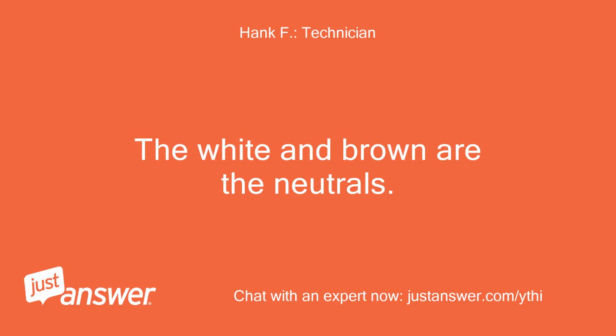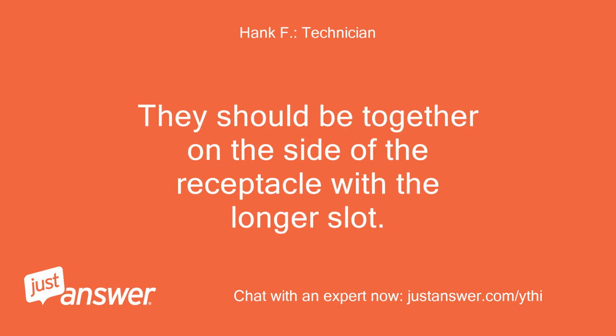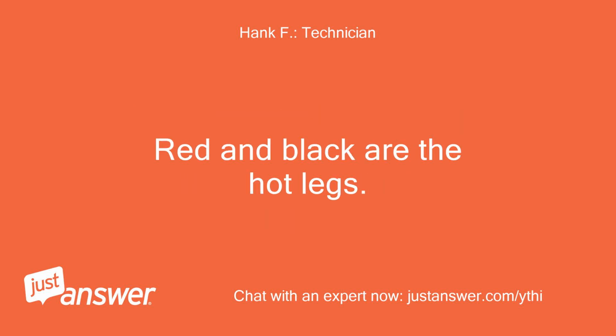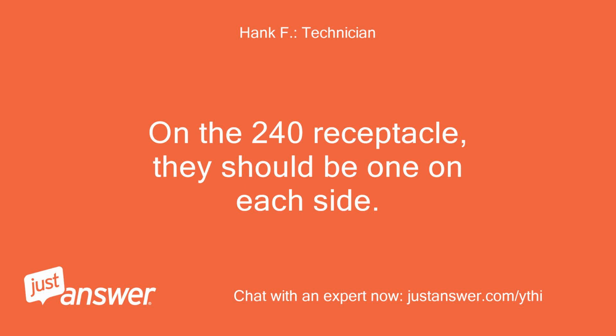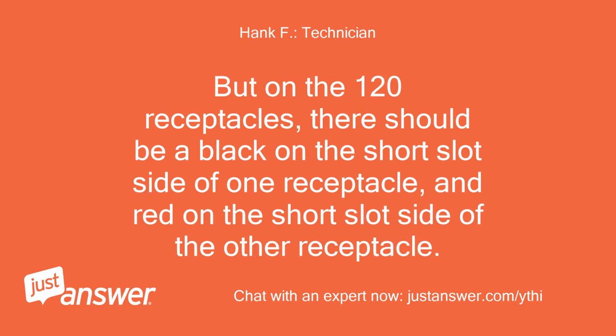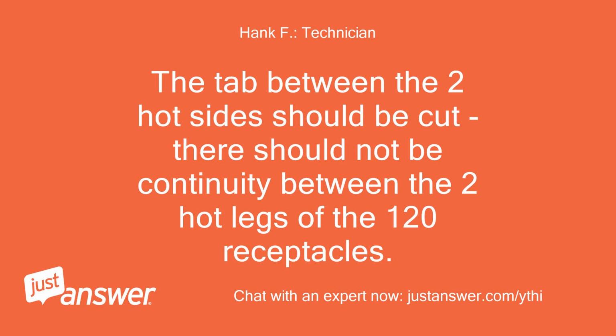The white and brown are the neutrals. They should be together on the side of the receptacle with the longer slot. Red and black are the hot legs. On the 240 receptacle, they should be one on each side. But on the 120 receptacles, there should be a black on the short slot side of one receptacle, and red on the short slot side of the other receptacle. The tab between the two hot sides should be cut. There should not be continuity between the two hot legs of the 120 receptacles.